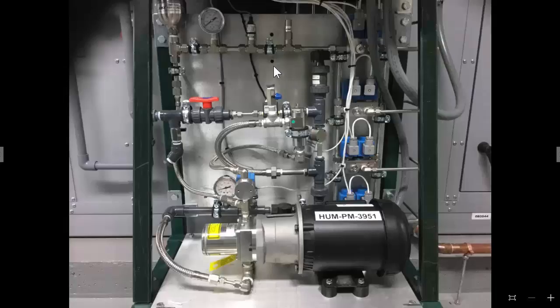Now I talked about the two functions of this pressure transmitter, low pressure alarm and high pressure alarm. But it does have a third function, and that is to provide the operating pressure, what the pump is operating at, back into the microcontroller, and to actually tell the microcontroller what the pressure is to regulate the speed of this pump. And if the demand changes, where the system wants more capacity, to increase the speed of the pump, which will also increase the pressure to give more capacity, humidification capacity. Now, I'm not going to talk any more than that about capacity control because I'm going to save that for a separate video. This is actually troubleshooting the high pressure side of the pump, but there is correlation there. So that's a start of bringing that up, and I may talk about it a little bit more in the benefit of troubleshooting, but that's it for now.